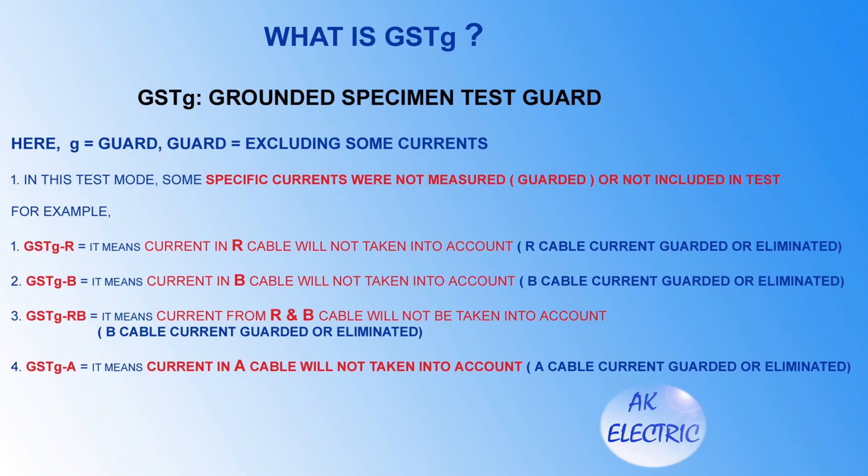What is GSTg? GSTg stands for Grounded Specimen Test Guard, where Guard means excluding or guarding some currents. In this test mode, some specific currents are not measured or not included. For example, GSDGR means the current in the red cable will not be taken into account — red cable current is guarded or eliminated.